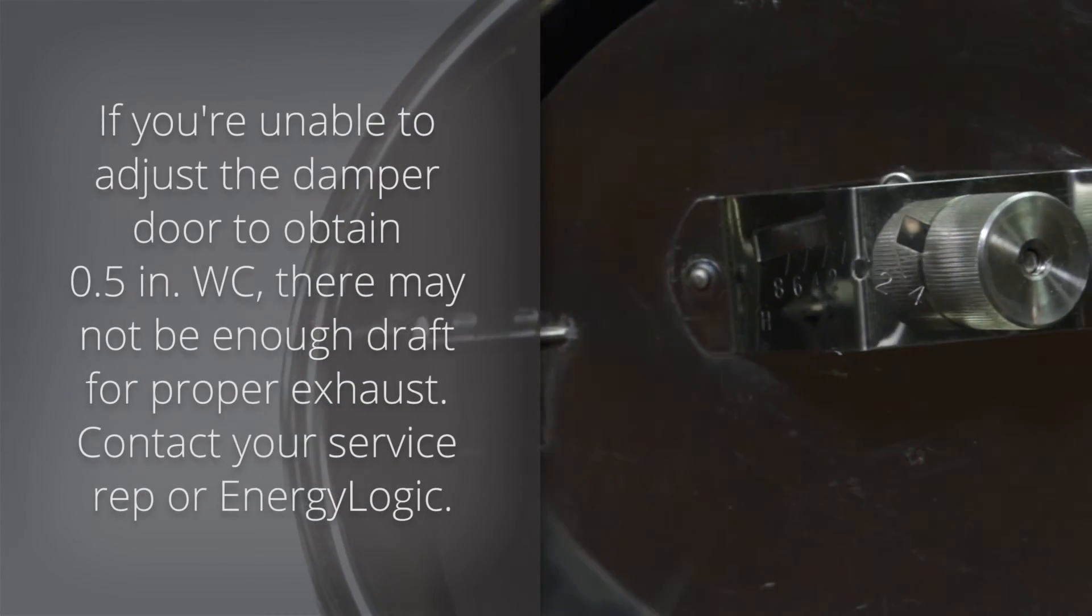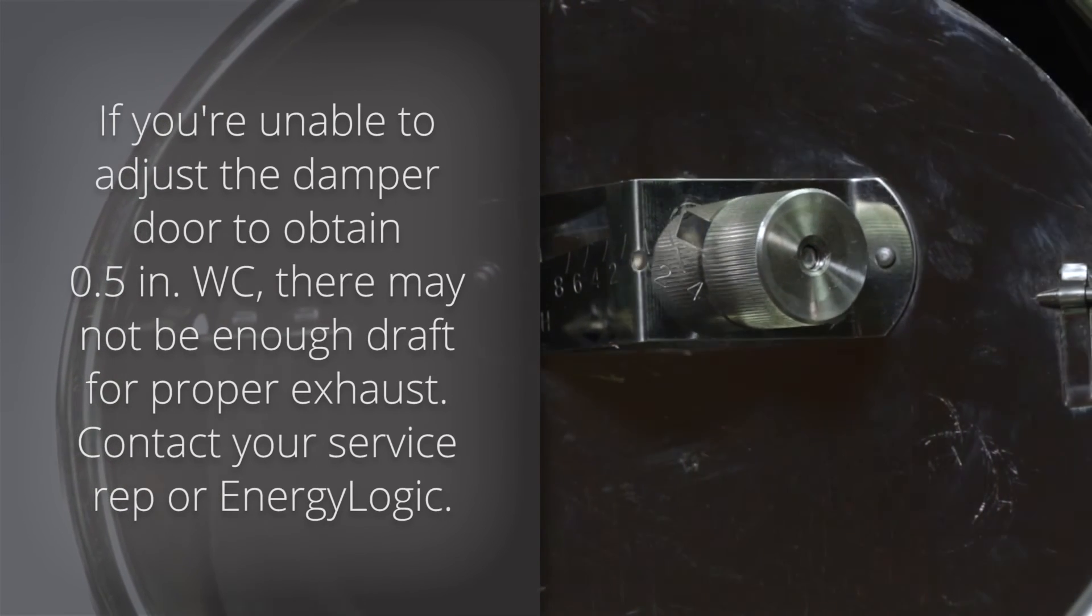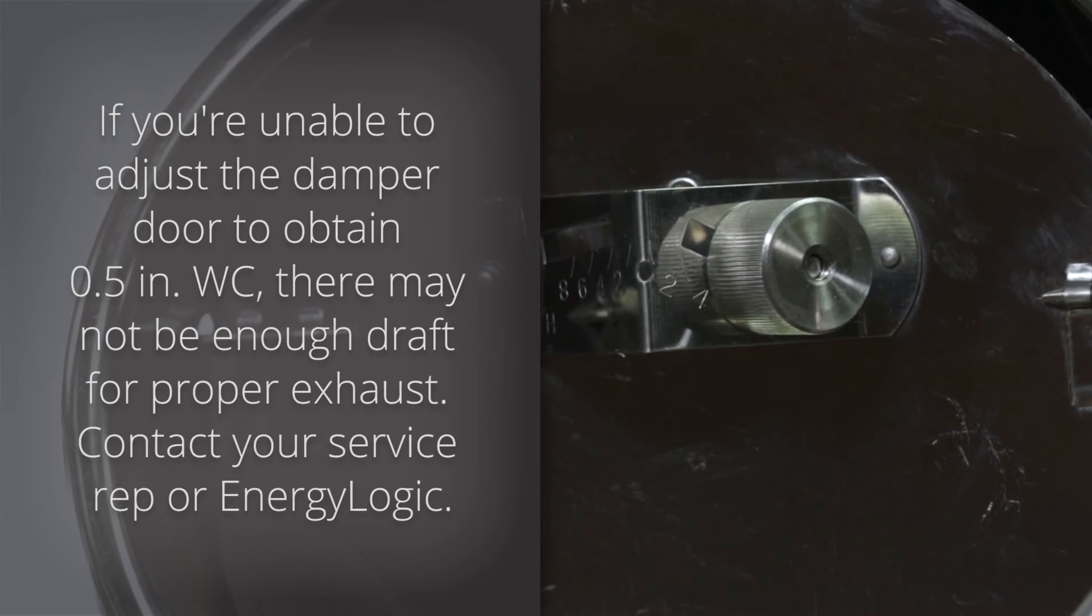If you are not able to adjust the damper door to obtain 0.05 inches of water column, there may not be enough draft for proper exhaust. Contact your service representative or EnergyLogic for further inspection.